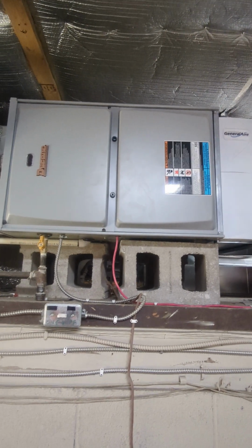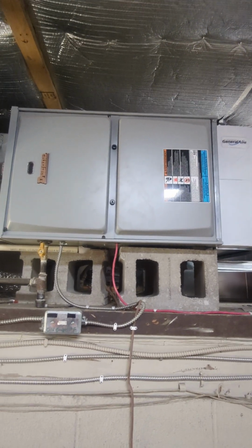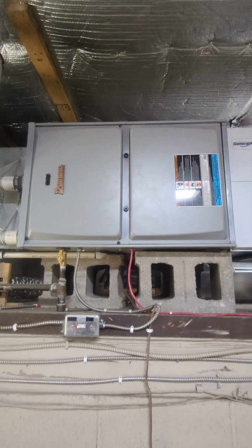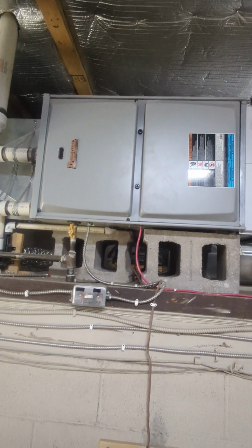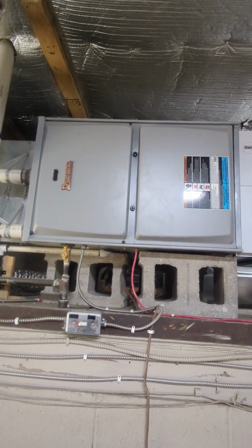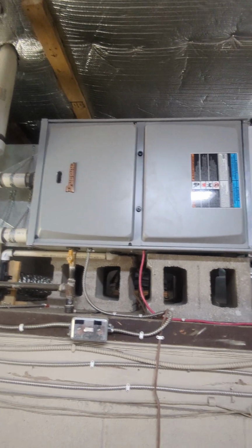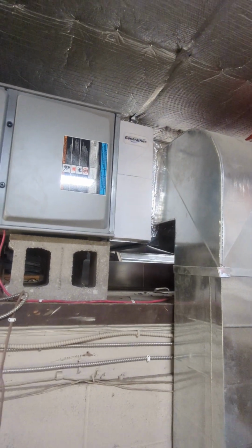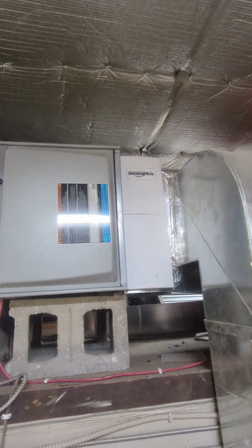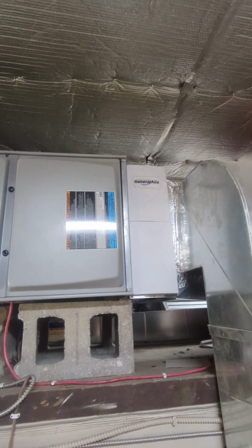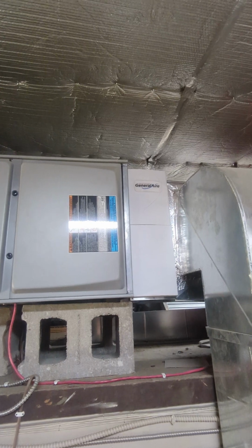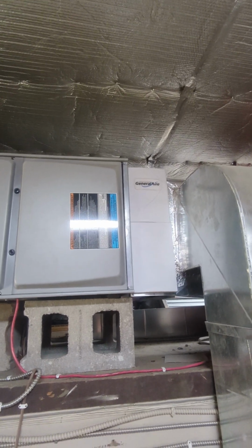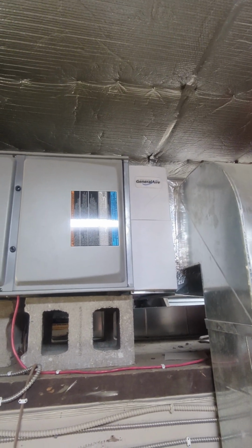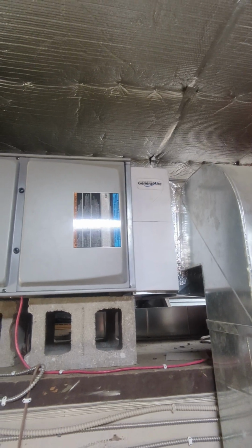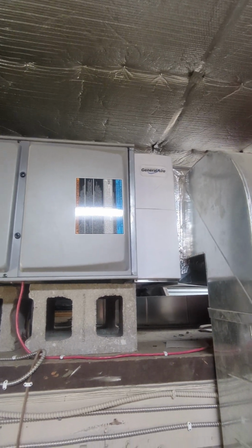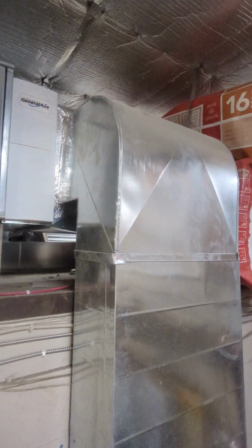Duquesne is produced by Allied Air, which makes companies such as Armstrong, Lennox, Duquesne, and Allied Air commercial equipment. That's like rooftop stuff, big equipment. So here's the return. That's a General Air PMAC filter system. So that's a 5-inch thick filter. With this size furnace being a 90,000, you need a 20 by 25 opening. So this filter is a 20 by 25 by 5 with large ductwork coming down for the return.